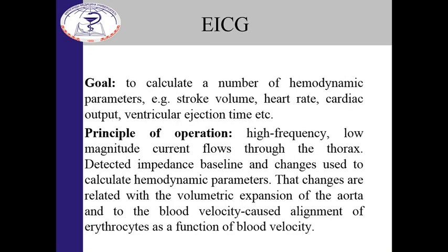Another technology based on totally the same physical principle, exactly measuring the impedance of the human body, is electric impedance cardiography. Its goal is to calculate, again calculate, not measure directly, hemodynamic parameters, like cardiac output and heart rate, or stroke volume and heart rate, which will be sufficient to get a cardiac output, etc. These values are based on, again, calculations, not a measurement. What we really measure is just an impedance.